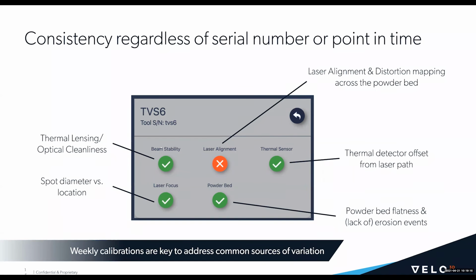So the first one is beam stability. This is basically verifying that the optical train is clean, because if there is debris on the optical train, then the spot will move as the optical train heats up. The debris will heat up and cause variation with respect to time and temperature. So we verify for that with beam stability.